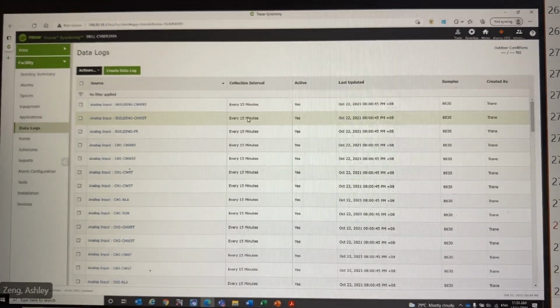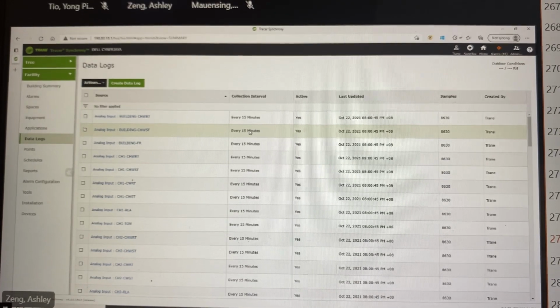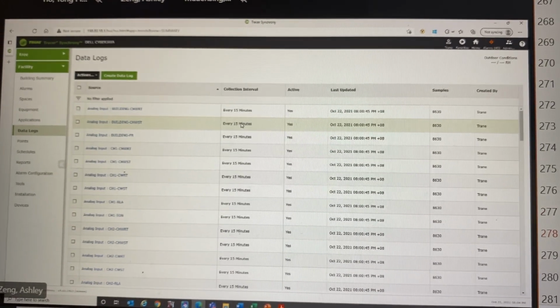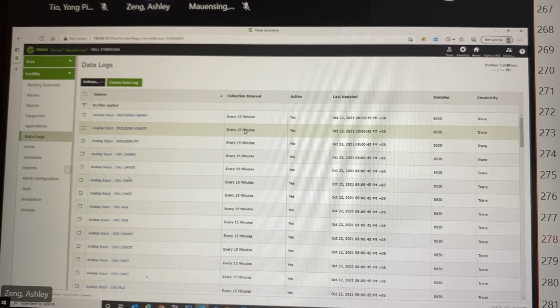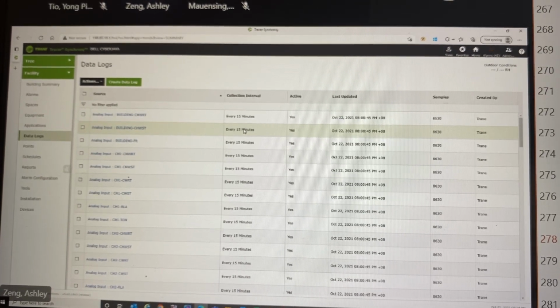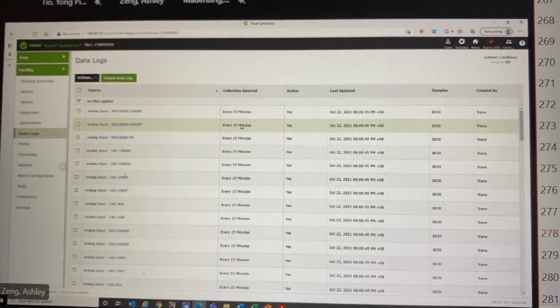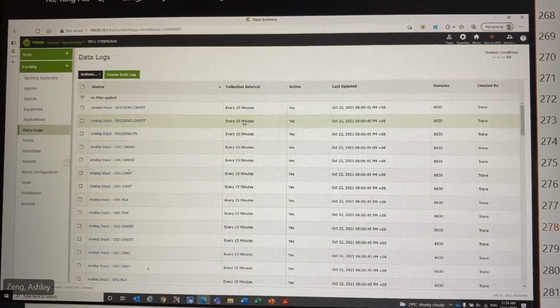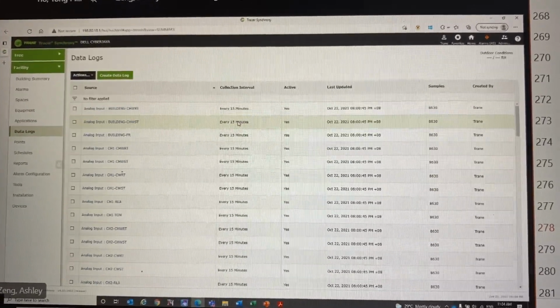We don't go beyond that because of our experience with the response time and reliability of the SE. So we cap it at 3, 5, or 7 days if we store chiller plant data at every 1 minute interval. For Singapore sites, because of BCA and NEA's requirements, we need to submit the data, so 1 minute interval is essential for chiller plant.